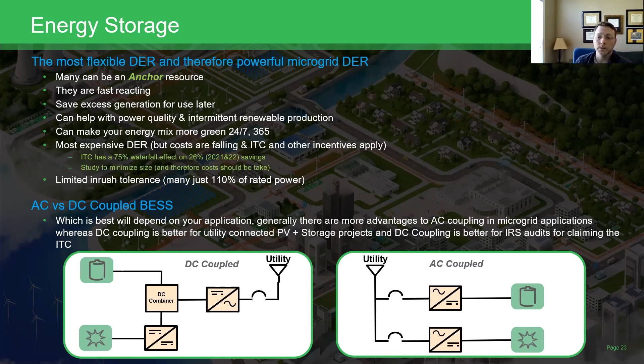And the reason I say that AC coupled systems are better for microgrid applications is really two main reasons. One is the DC coupled system has a single point of failure with one inverter here. And the other is that, let's just imagine this is 100 kilowatts of battery and a 100 kilowatt PV array behind a 100 kilowatt inverter. In the same scenario with the AC coupled system, if we had a 100 kilowatt battery, 100 kilowatt PV array, we have an additive effect where we have 200 kilowatts of potential power to support loads. So we can support more in an AC coupled system.